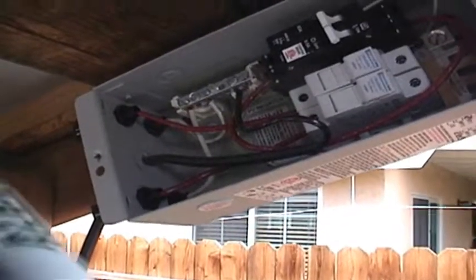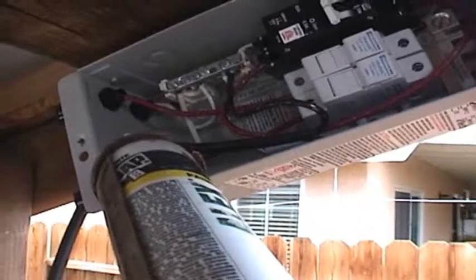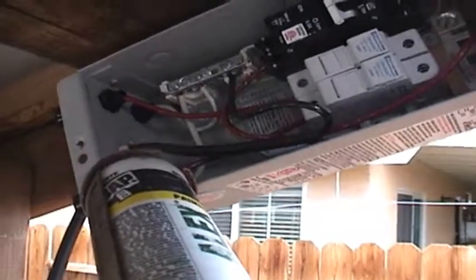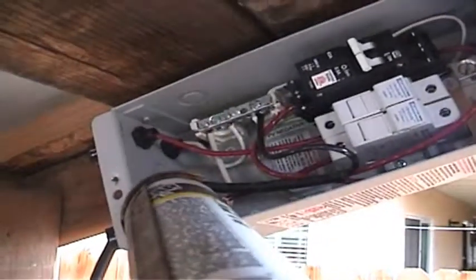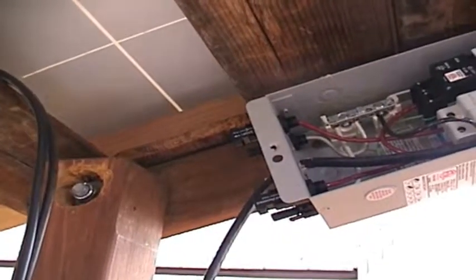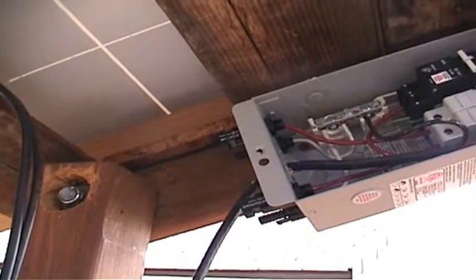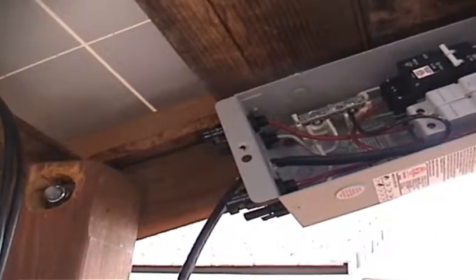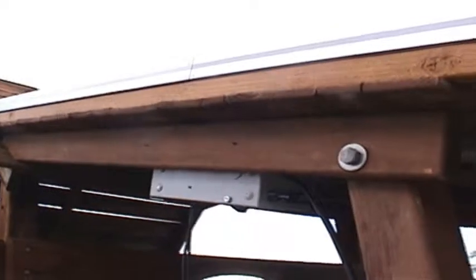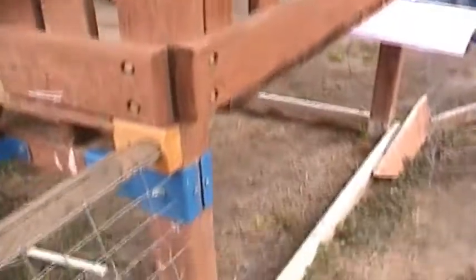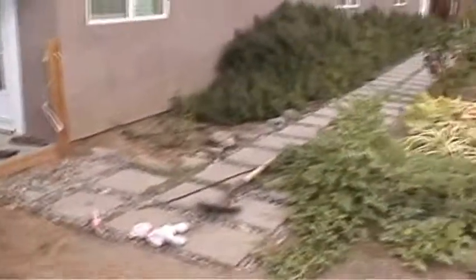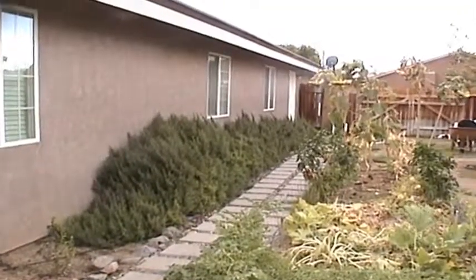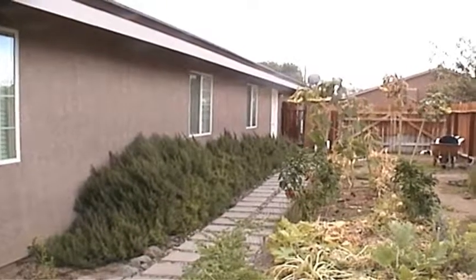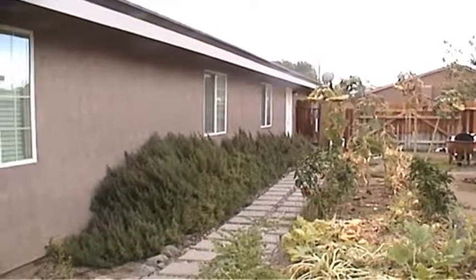With our combiner box now secured, I'm going to put a little bit of RTV in the hole where the outdoor cable comes through into the combiner box. And remember, don't connect the solar panel cables into the combiner box yet. That will come at a later time. Our combiner box is now connected beneath our solar panels, and we've run our outdoor wire all the way down into our trench through some PVC pipe along the wall of our house behind those bushes into the garage and to our battery bank. This step is now complete.